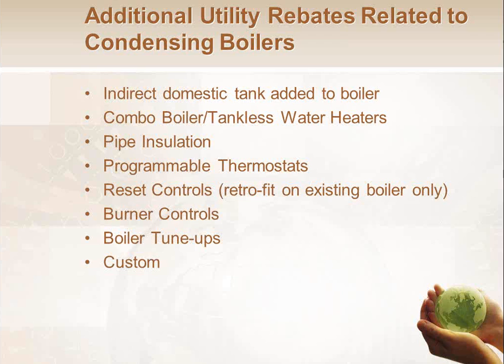On the commercial side, you'll often see rebates for adding reset controls to an existing boiler. You don't get that rebate for a new boiler because for a new boiler, you pretty much have to do it by law anyway, either residentially via the DOE rule I just talked about or commercially via the building code.